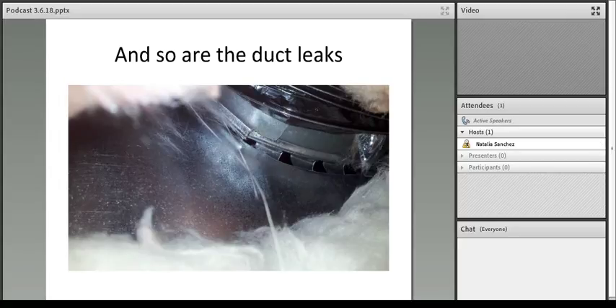And, yep, that's unfortunate, and it's the homeowner who has to deal with it. Yep. So yeah. If those ducts were inside the house and they were leaking out, well, it's lack of supply air, but the BTUs aren't lost to the outside. In this case, they're lost. If I lose that air, I have to make up that air in the house. So I have to bring outside air in because I'm pushing conditioned air out. The house is a finite amount of volume, right, and any pressure exerted across it forces air to go in or out.